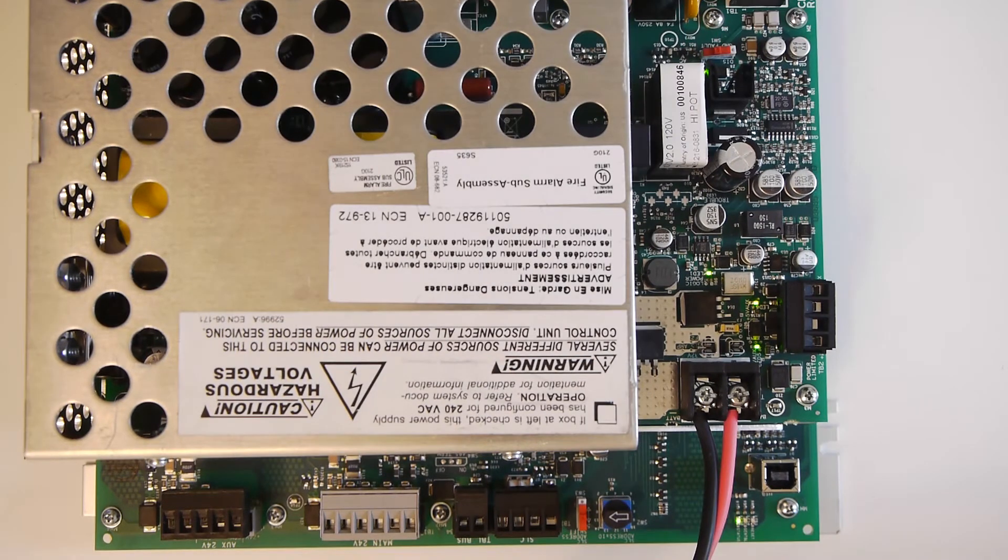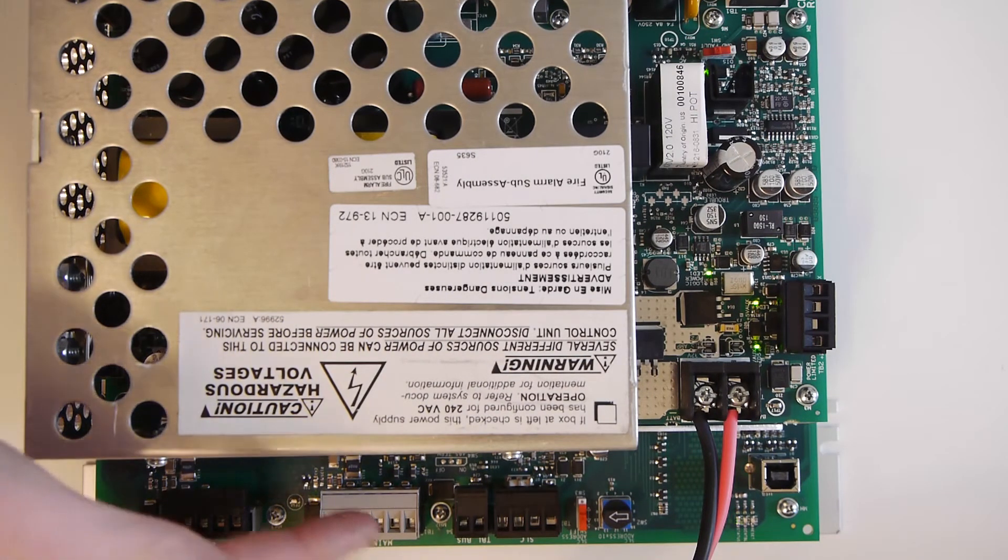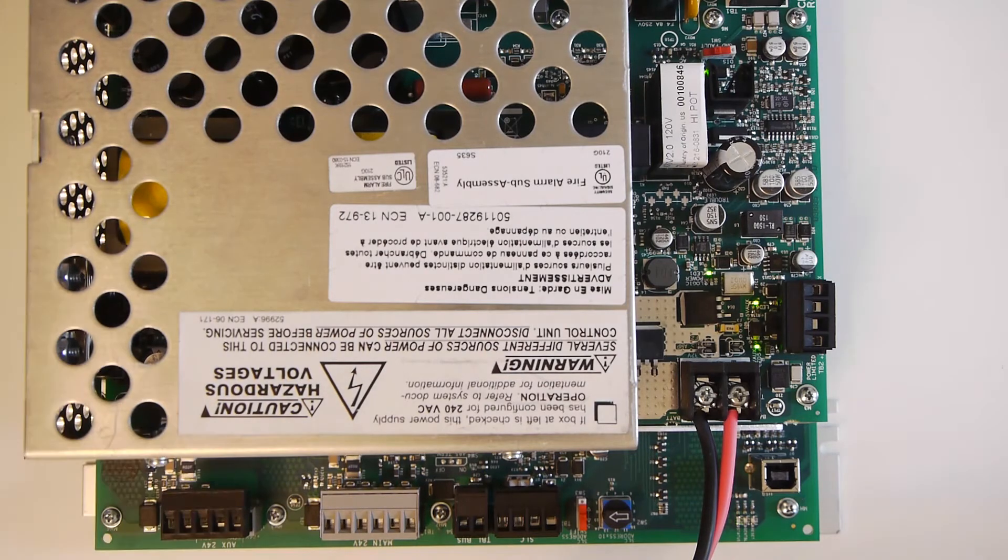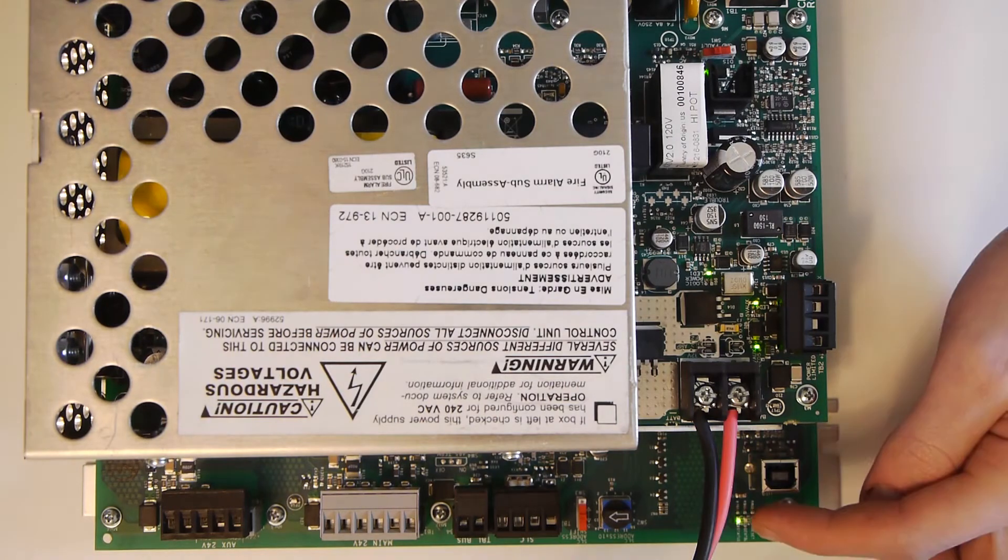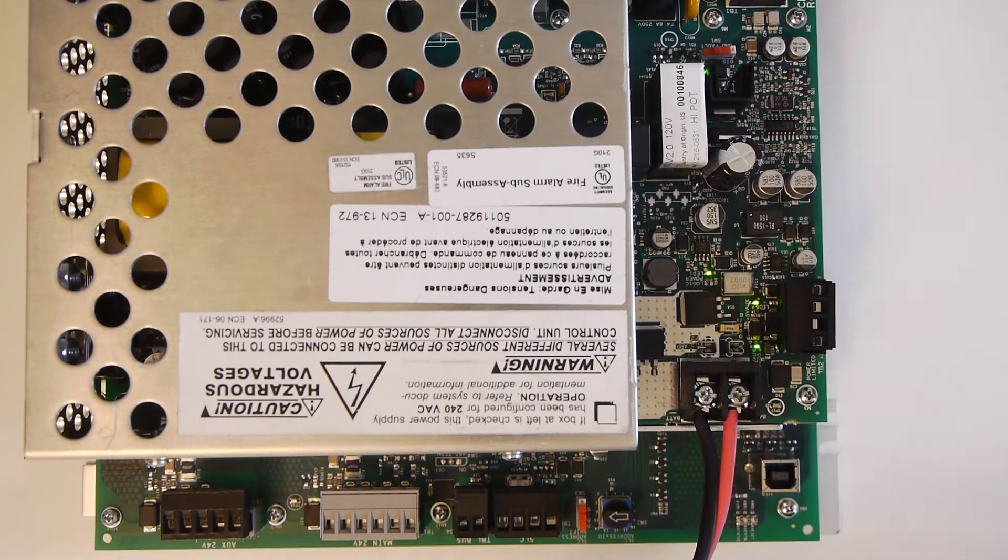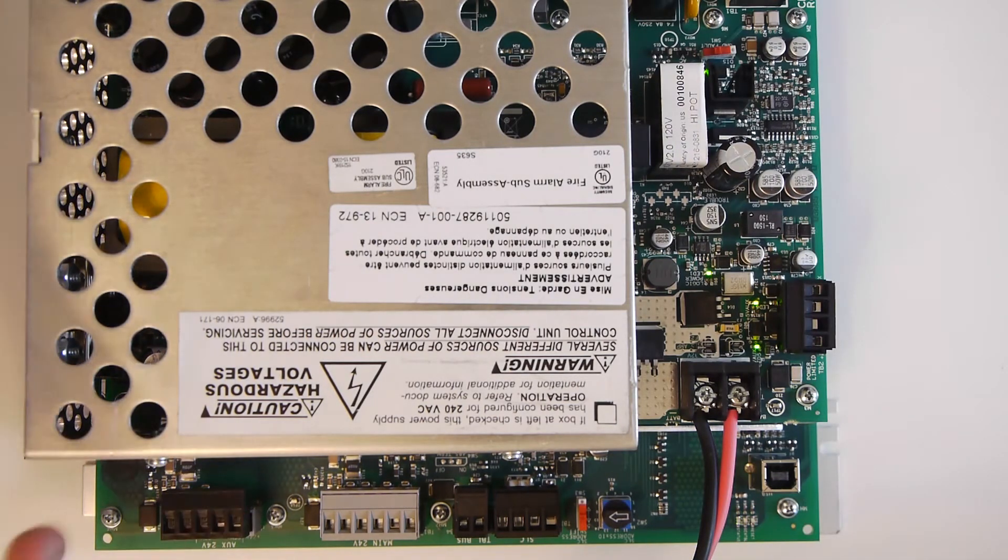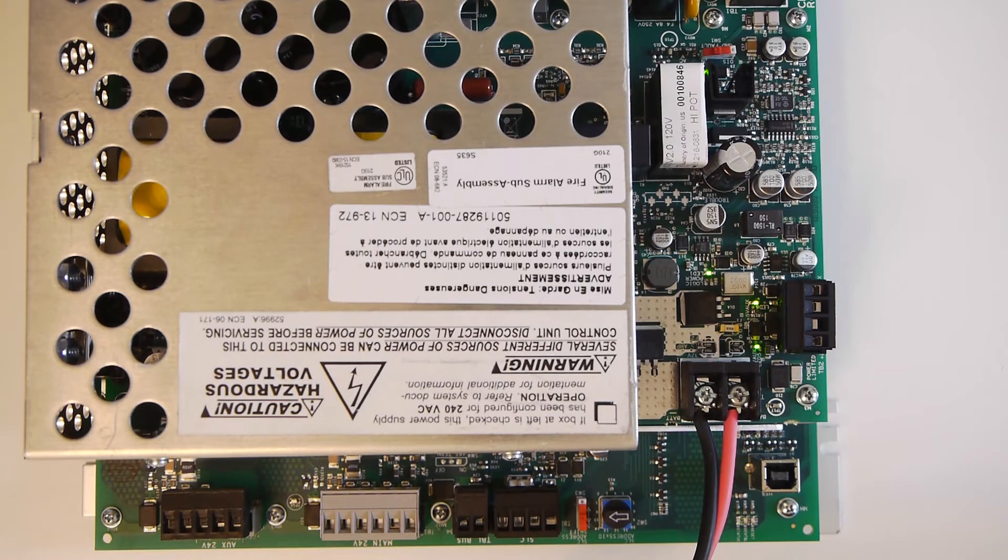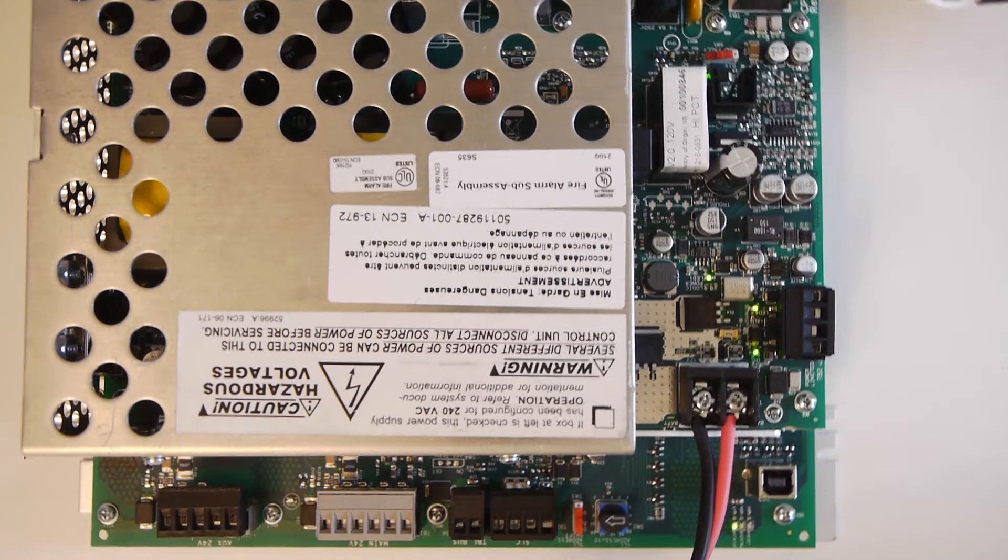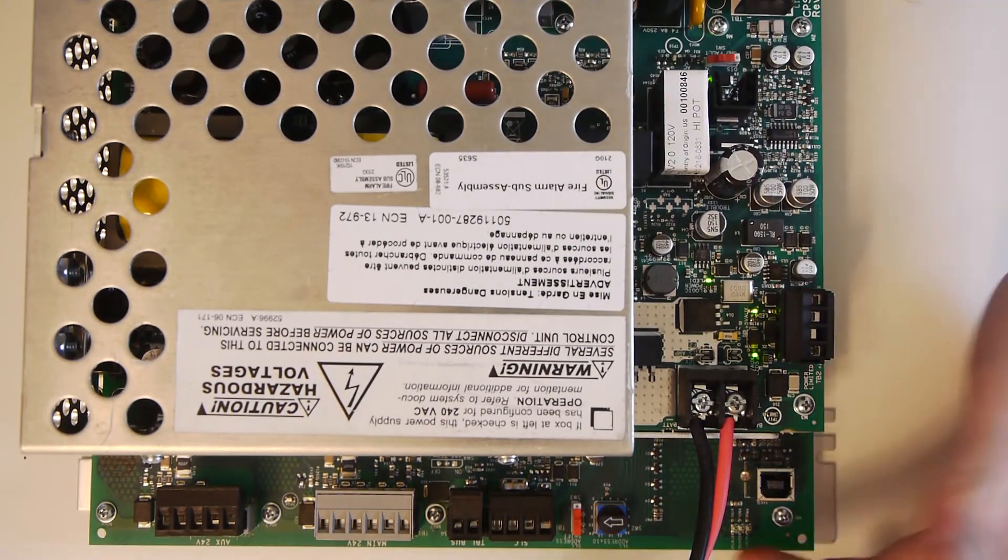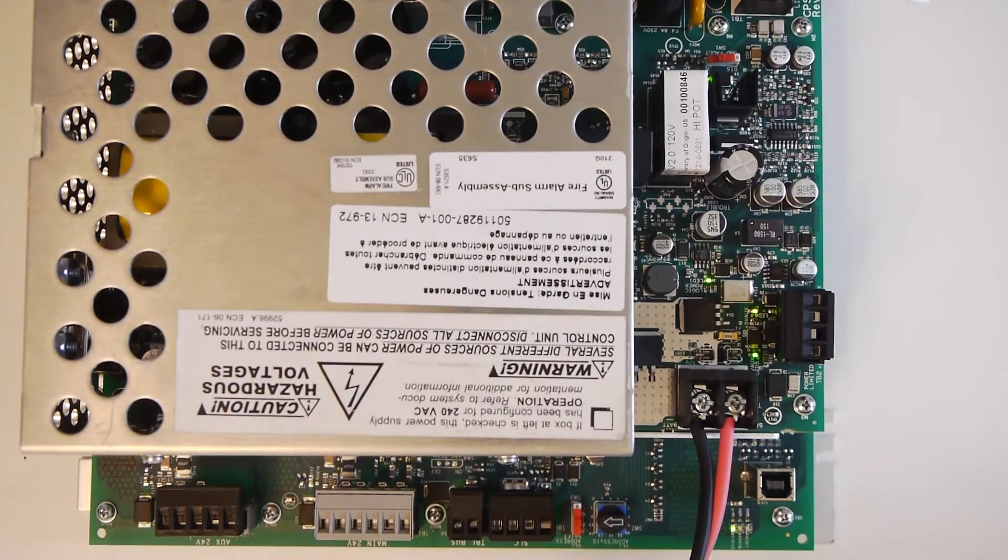Now on the AMPS 24 board, there's a light right here and a light right here, which just are on to show you that both the outputs are outputting power. And right here there's a blinking green status light. Now I'm not sure this light right here will go solid green if it is communicating with the panel or the SLC circuit or anything. I don't have a panel to hook it up to yet, so I'm not sure. But right now it has batteries, it's programmed, and it has AC power. So it just blinks green, I think, when it's normal.